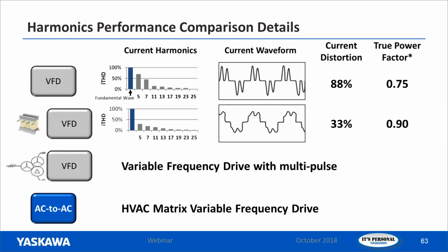Here, just by adding a DC bus reactor, we're getting that current distortion down to 33%. That's a massive cut from the 88%. And we've got a 0.90 power factor. Every Z1000 drive has a built-in 5% DC bus impedance, so you're not paying extra for it, we just have it built in. We're already getting you down to as low as 33%. You're going to be in the 30s range for sure.